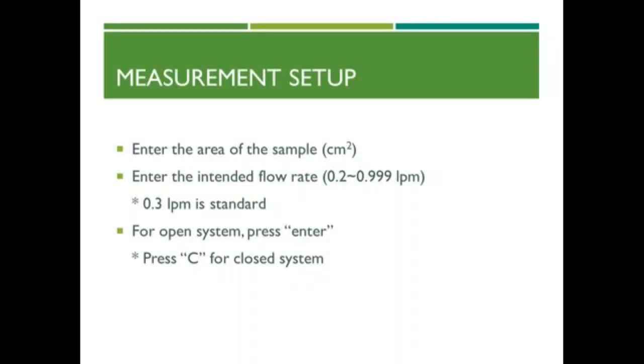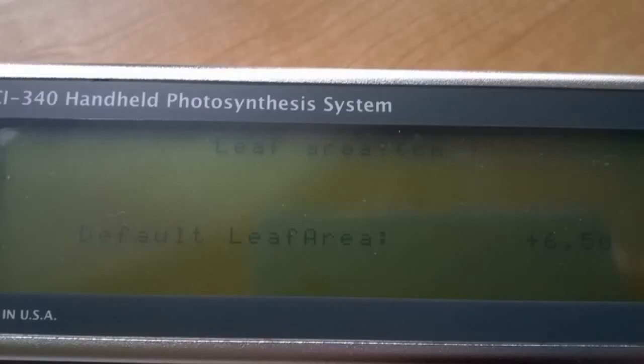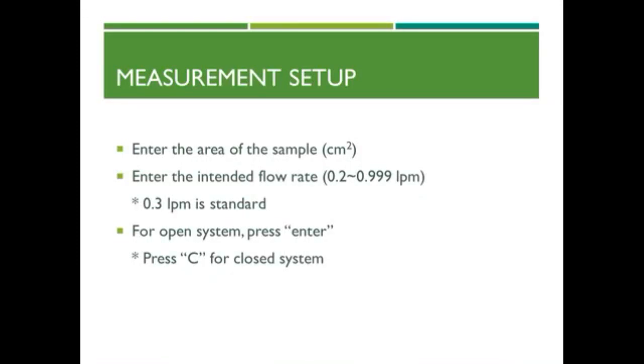The display will read Leaf Area in centimeters squared. Enter the area of the leaf sample, or the area of the window if the leaf takes up the entire chamber, and press Start. Each leaf chamber has the area printed on it. The CI-340 will remember the last leaf area entered as the default.